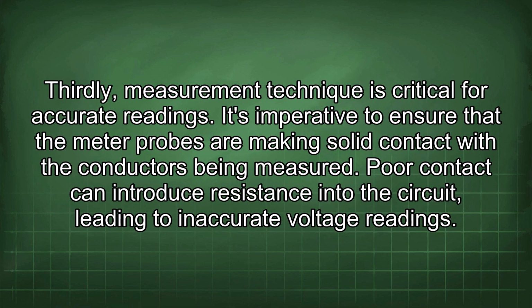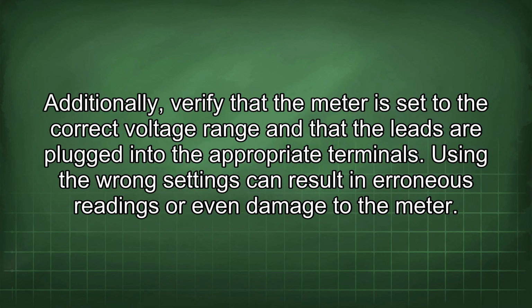Thirdly, measurement technique is critical for accurate readings. It's imperative to ensure that the meter probes are making solid contact with the conductors being measured. Poor contact can introduce resistance into the circuit, leading to inaccurate voltage readings. Additionally, verify that the meter is set to the correct voltage range and that the leads are plugged into the appropriate terminals. Using the wrong settings can result in erroneous readings or even damage to the meter.